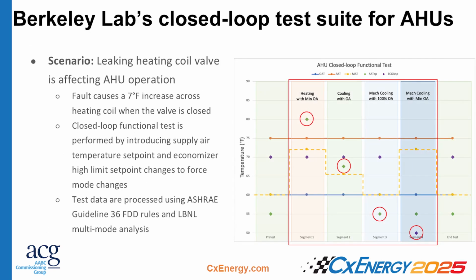So this is an example of what I talk about when I say follow-up testing and the value of having these different modes. Number one, with a passive FDD tool, you would be able to pick up these faults, but only in certain seasons. If it's a heating fault, for instance, you're only going to really get that when the boiler's on, or you have heating conditions happening. But you won't get any heating faults figured out in the other times of the year. So in a normal, business as usual test case right now, you would really need a whole year's worth of data to get the full breadth and understand the condition of the air handling unit. But with a functional test like this, where you're driving the different modes, you could get that full year's picture all within a span of a few hours, right? And that's something that I think is pretty powerful here.